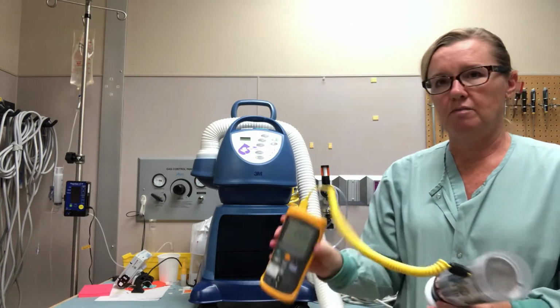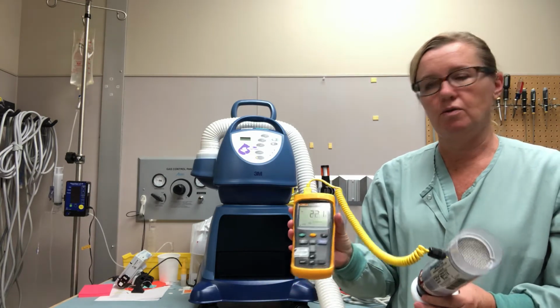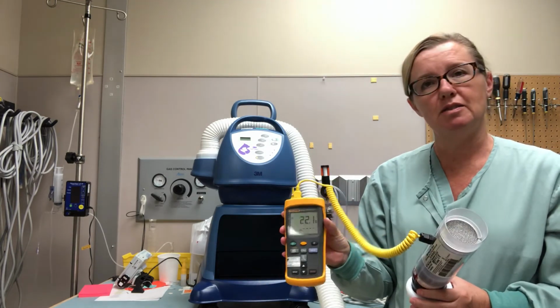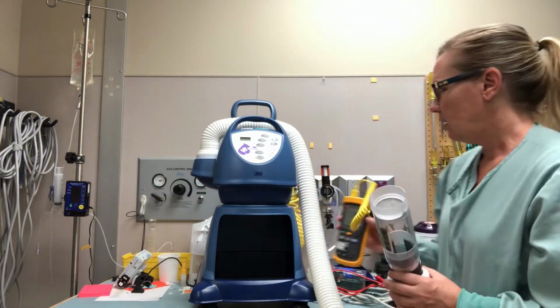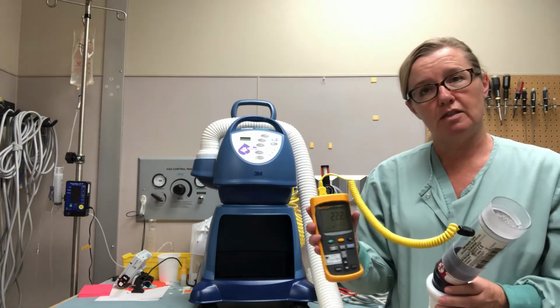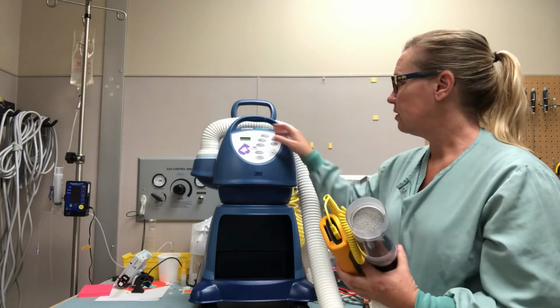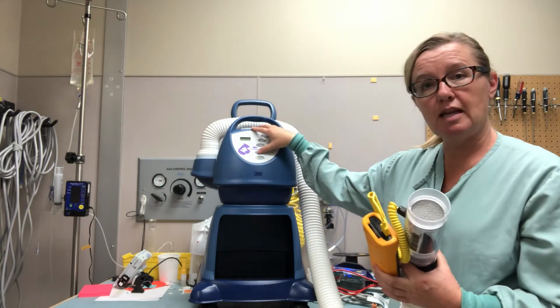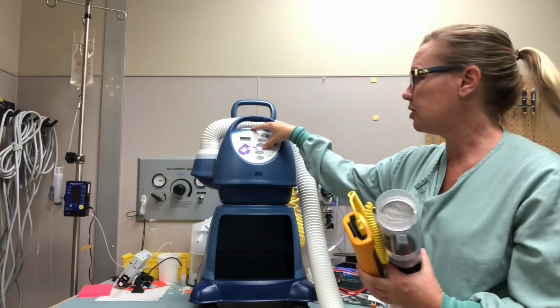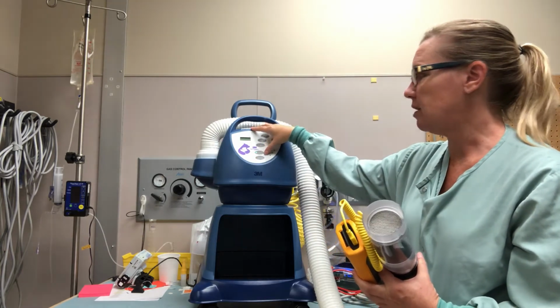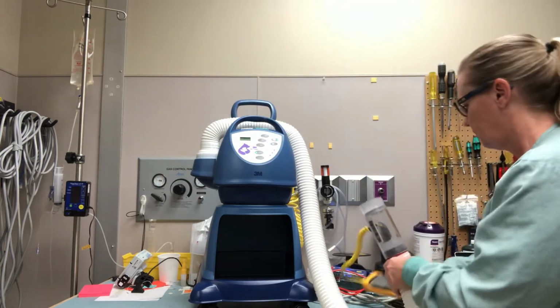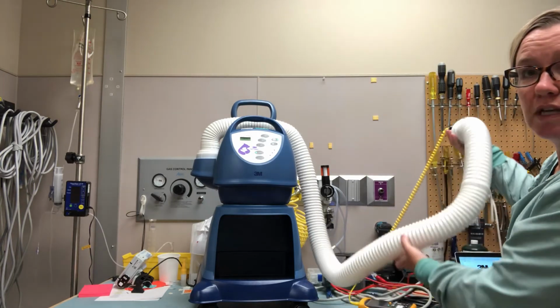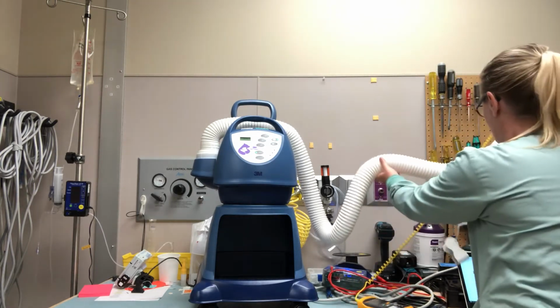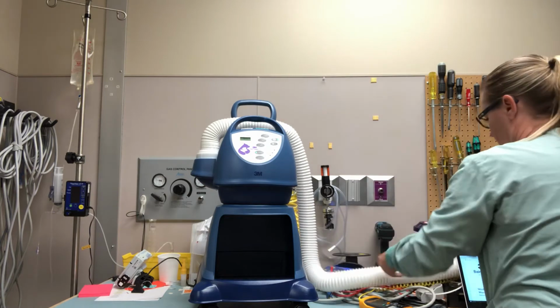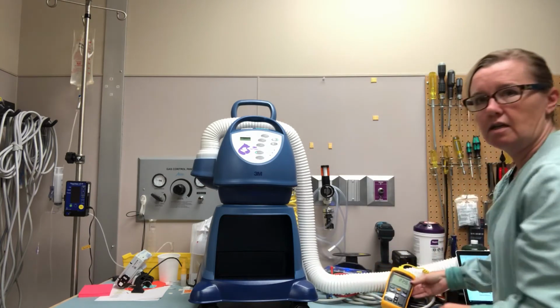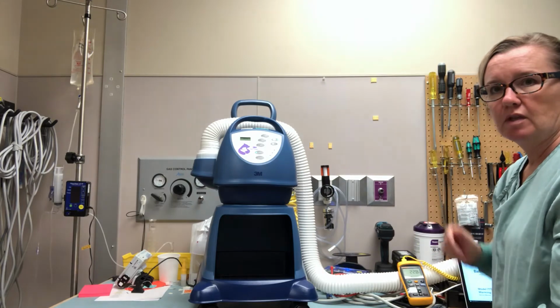So right now my thermometer is reading about 22 degrees Celsius, so that's room temperature. And that's what we're gonna test our operating temperature with. We're gonna test it at ambient, which is room temperature. So I'm gonna hit the ambient button here. I'm gonna make sure my hose is straight so there's no kinks, no obstructions. And we'll just let that go.